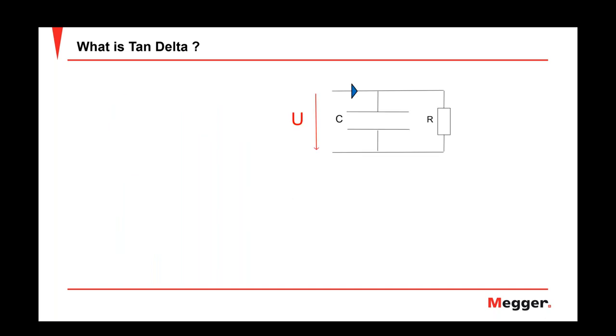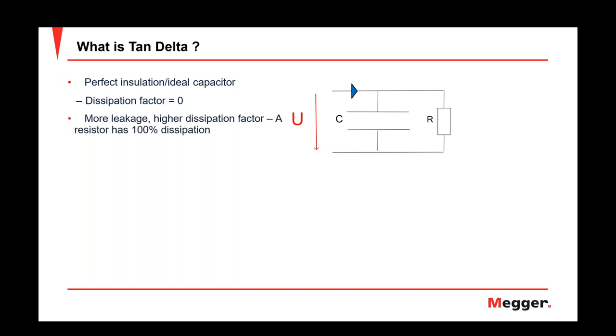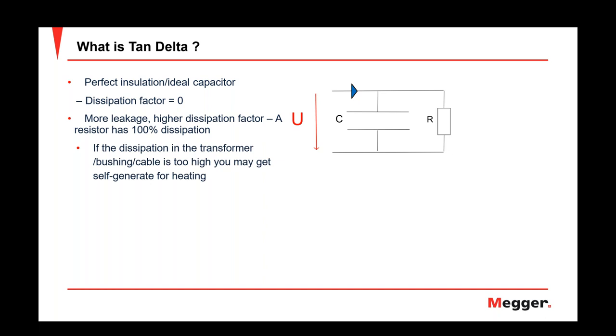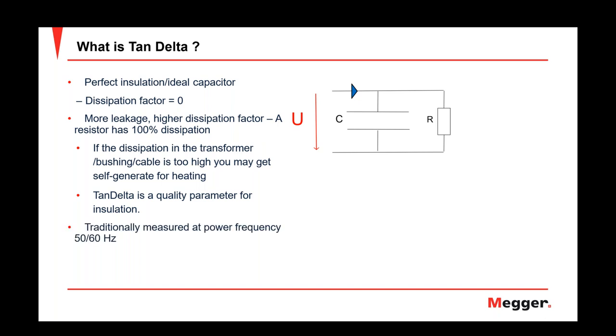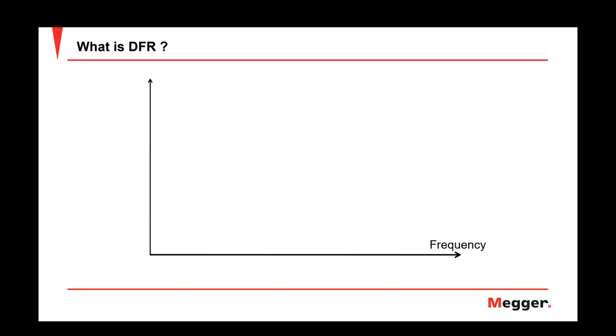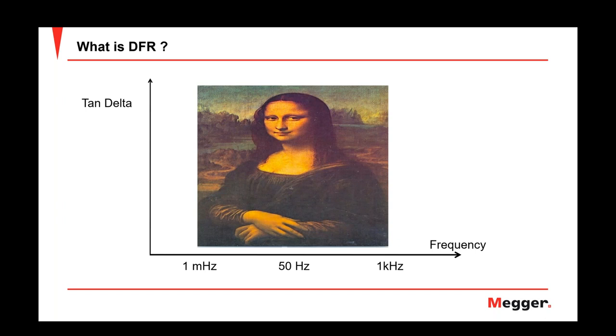A perfect insulation is like an ideal capacitor with a very low dissipation factor. The more leakage, the more dissipation factor, and the worse the insulation. If dissipation in a transformer, bushing, or cable is too high, you may get self-generated heating. So tan delta is a quality parameter for insulation, and traditionally we measure it at 50 Hz. DFR — Dielectric Frequency Response — takes that further: instead of measuring tan delta only at 50 Hz, we measure it across a range of frequencies to complete the picture.